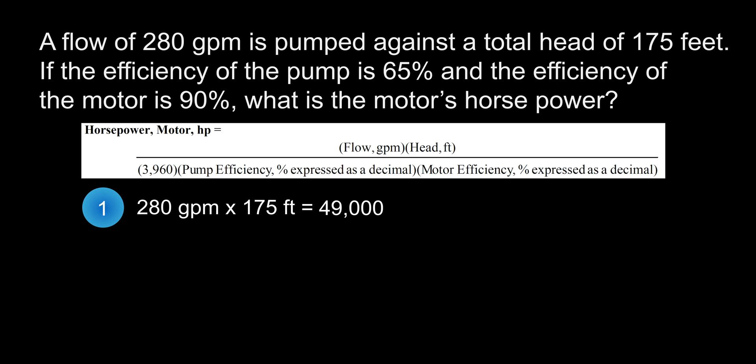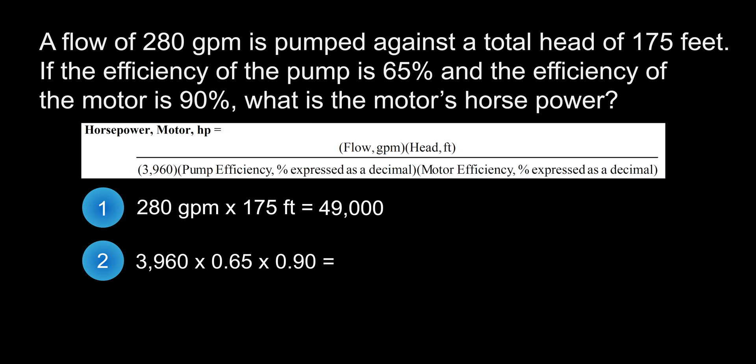Next, we will solve for the bottom half of the formula. We do this by taking 3,960 — which is a constant that is necessary for the conversion to horsepower — and multiplying it by the pump efficiency of 65%. Converting 65% to a decimal gives 0.65. We then multiply that by the motor efficiency of 90%, converted to a decimal, which is 0.90. This gives us an answer of 2,316.